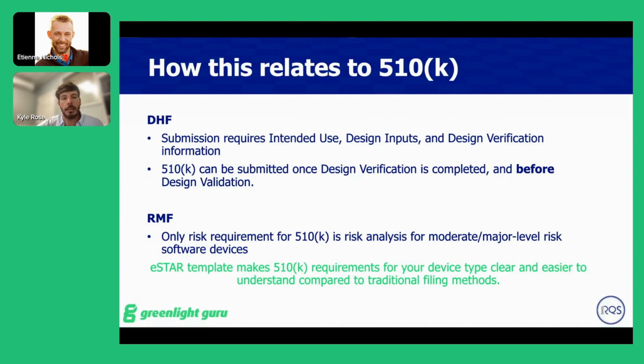Some of the things that may not be in your submission, but should be in your design control, would be your user needs, your design inputs, and your risk analysis. A lot of times, risk analysis is not required for hardware devices or electrical devices, but it is required for software. So in your 510K, a lot of times it really is your design outputs, your verification and validation activity, your substantial equivalence argument, and then your labeling and packaging. So just be aware that you still need to do this stuff, but it might not all be in your 510K.